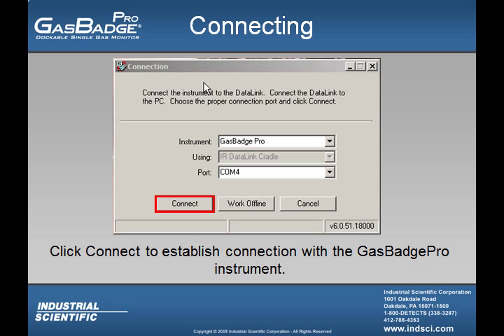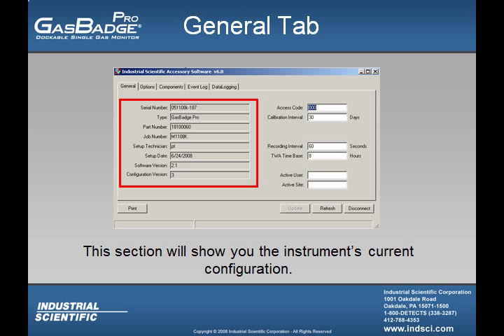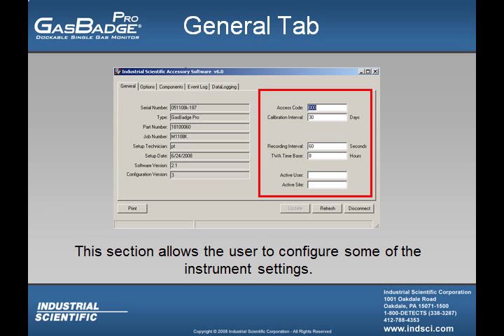After the user has ensured that both selections are correct and the Gas Badge Pro is inserted into the Datalink, they can press the Connect button to establish connection with the Gas Badge Pro. Once connected, this is the main screen for the particular Gas Badge Pro inserted into the Datalink. The section on the left shows the Gas Badge Pro's current configuration, and the section on the right allows the user to change some of the instrument features.